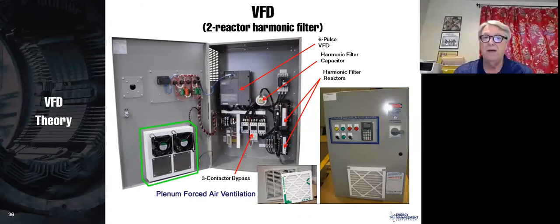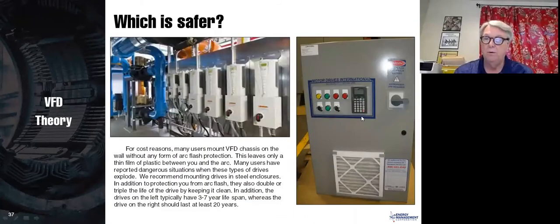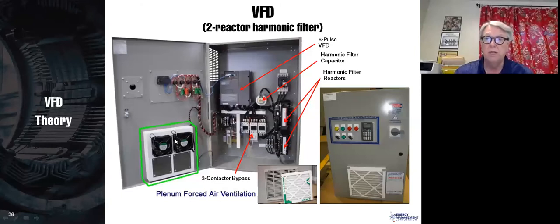Here is a drive that is fan cooled. We really like fan cooled enclosures because they keep the drive clean. A drive like this should give you 20 years of life because that drive stays very clean on the inside. And we mount our filters right out here where you could see them rather than behind louvers, because we find that putting our filters behind louvers, people forget to change the filters. So obviously, if you have filters, you need them. If you want a really heavy-duty industrial drive, this is what you should get.